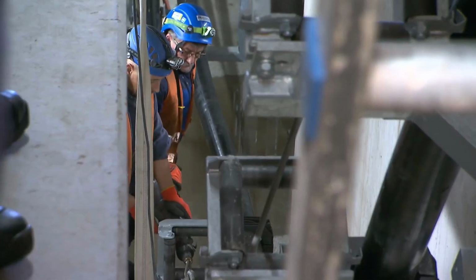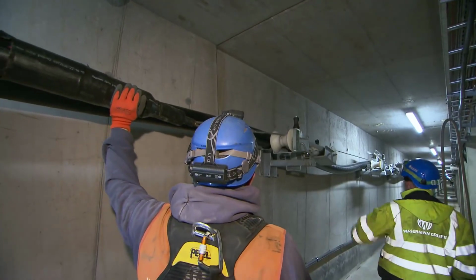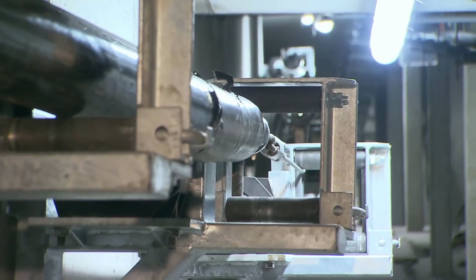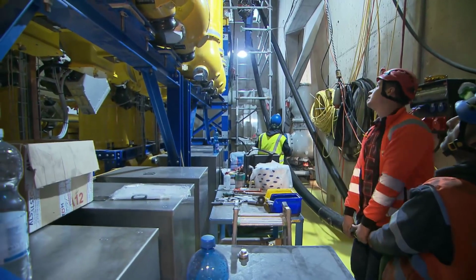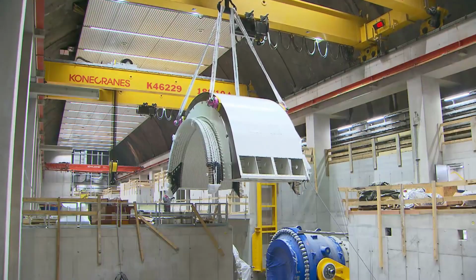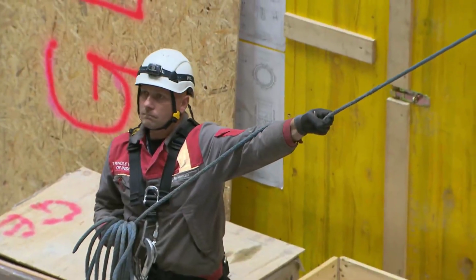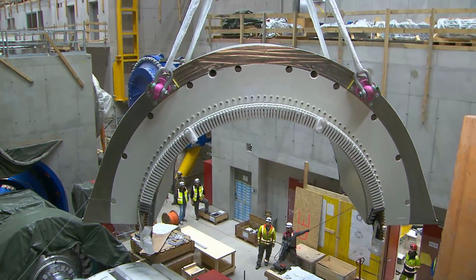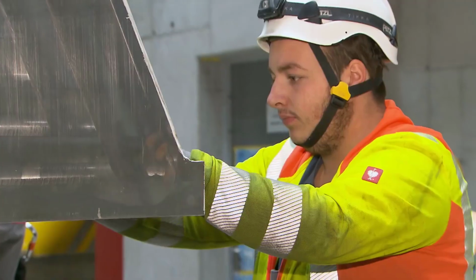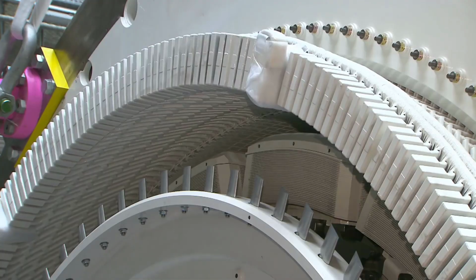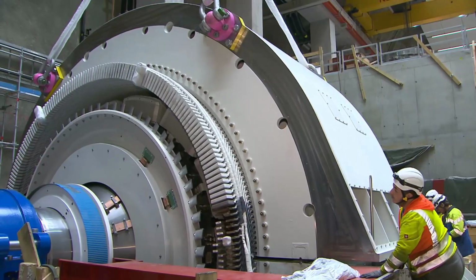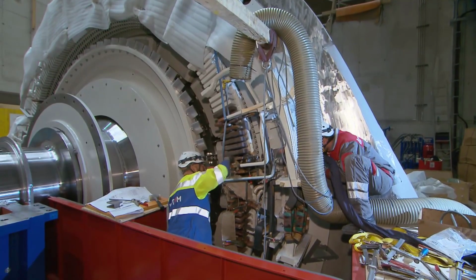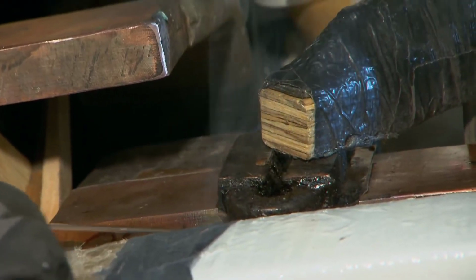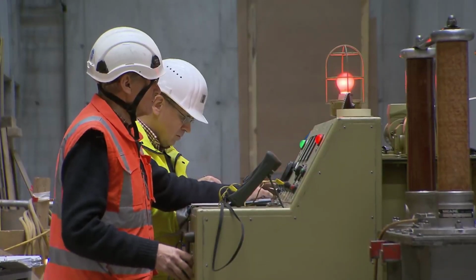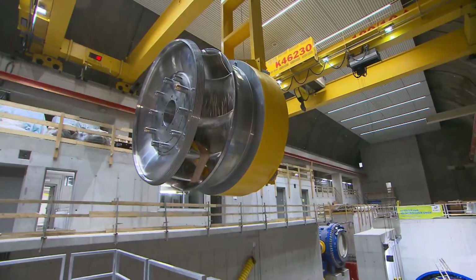The exposed sections in the steep stretch where the cables lie are covered, and later greened to preserve the landscape and wildlife. The completion of the cable and escape tunnel, with the aid of push devices and winches, to the 220 kilovolt switchgear is underway. In the machine cavern, the completion of the first set of machines is progressing rapidly. The upper stator half, weighing 112 tons, is now placed on the lower stator half and bolted together, with the movable rotor in between. In the transition area between the two halves, the bars still need to be soldered and insulated. The general assembly is completed with the high-voltage test on both machines.